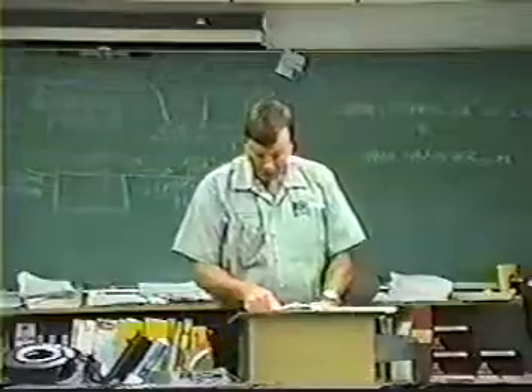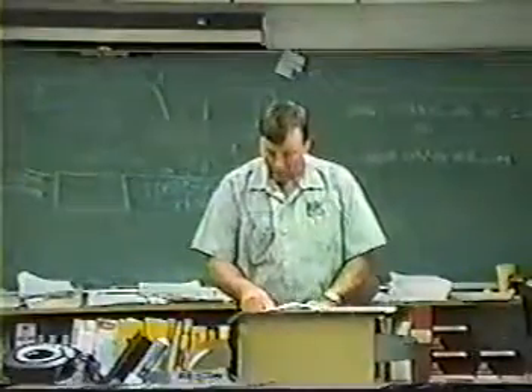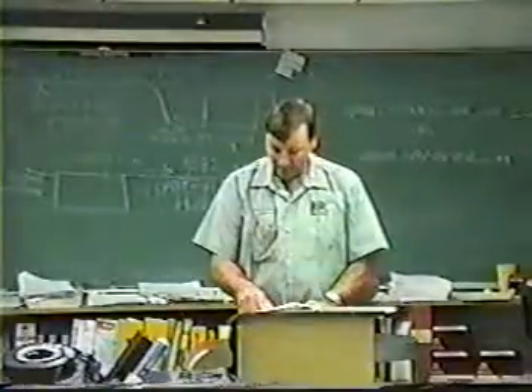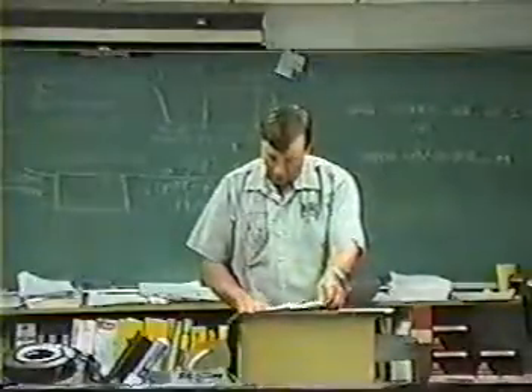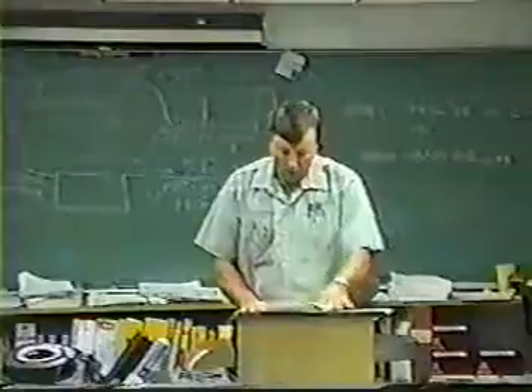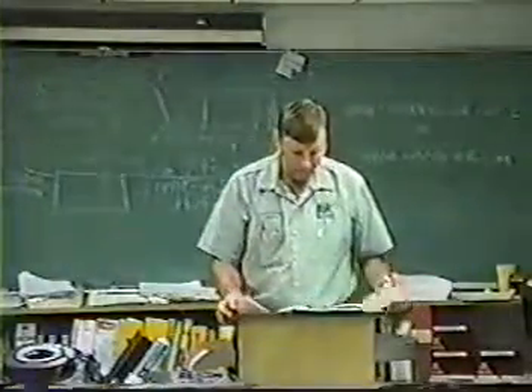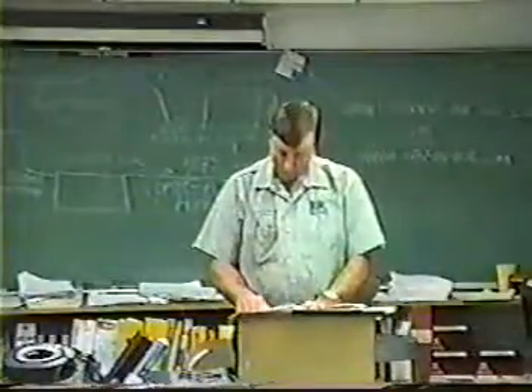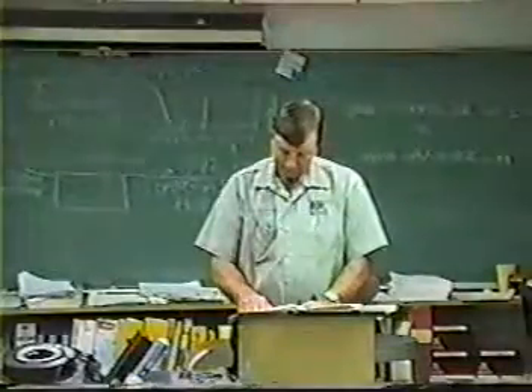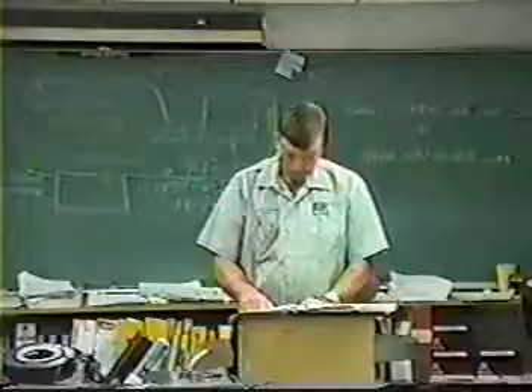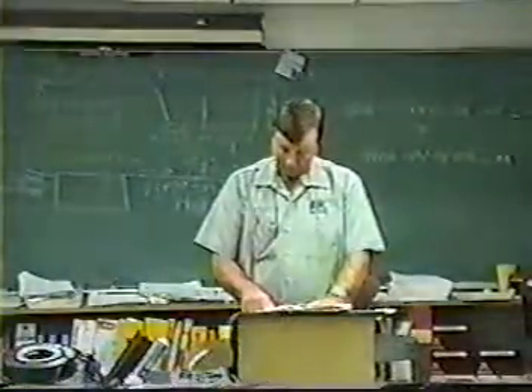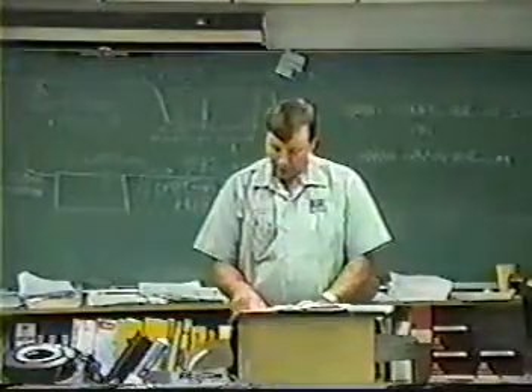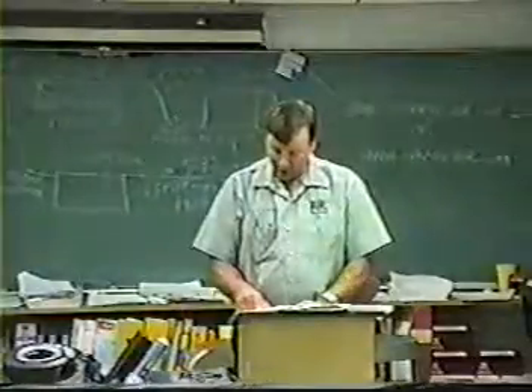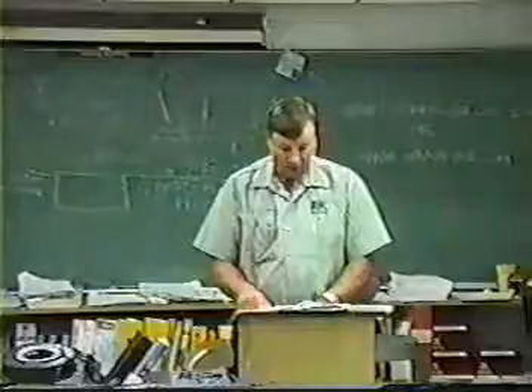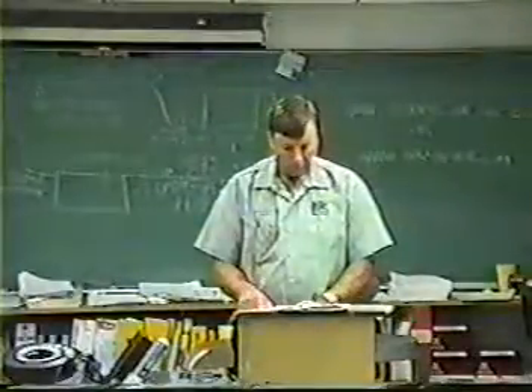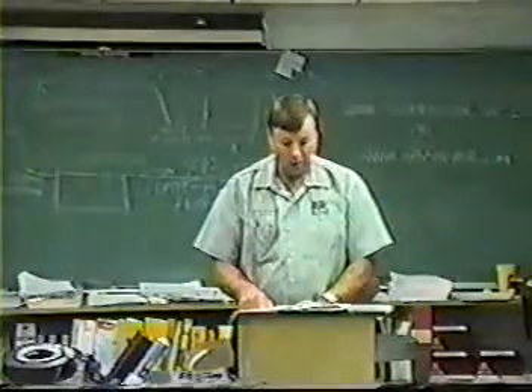Move on to number 56. The required level of evacuation for recovery equipment manufactured before November 15, 1993 on a system with R22 charge of less than 200 pounds. All right, move back to page 11. Now, what's the answer, guys? I was looking at the wrong question. The required level of evacuation for recovery before November 15, 1993. That's the key, before, on a system of less than 200 pounds. 0. You guys see that now? The very top one on the left is 0.